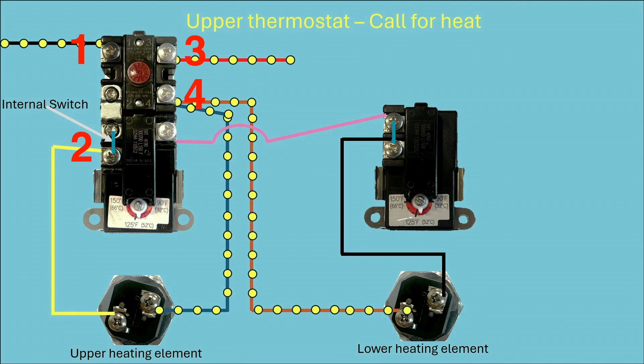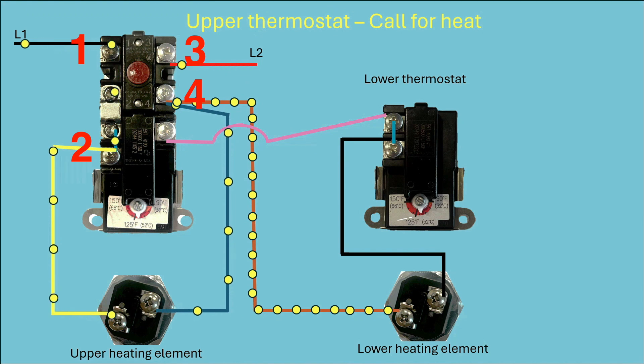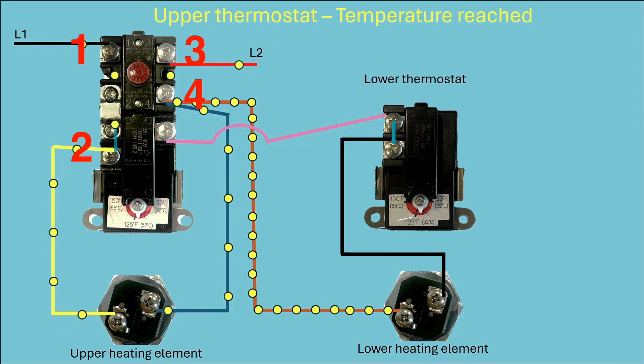So when this thermostat detects that the water temperature is below the set point, it will close that switch, which I'm showing in blue, and it will therefore basically produce a call for heat. And that will cause the current to start flowing. And you can see it flowing from screw four down the blue wire into the heating element and up the yellow wire and back and across that internal switch. And then at some point, the temperature set point will be reached. And you can see this blue switch starting to flash now. And that switch will open up and it will stop that current from flowing.